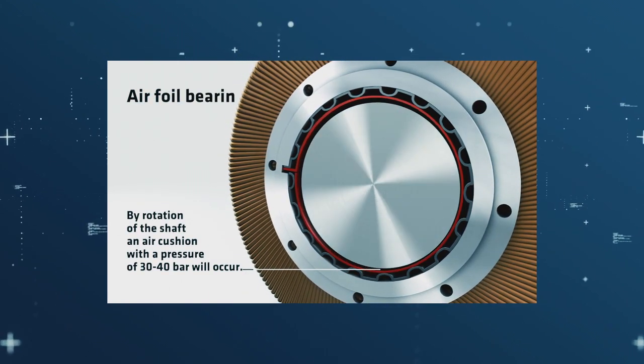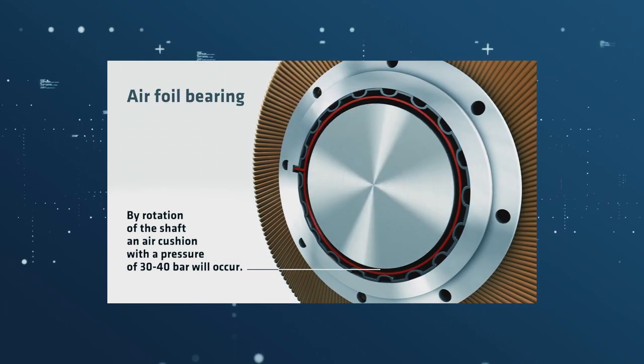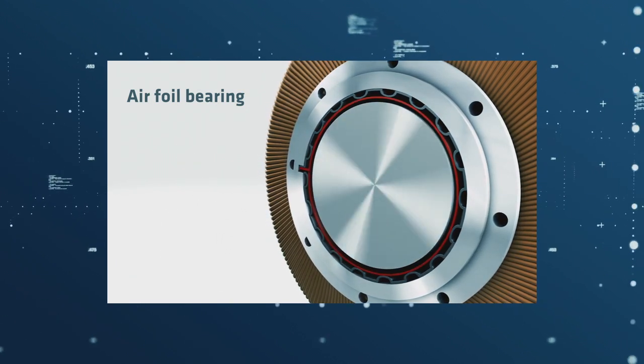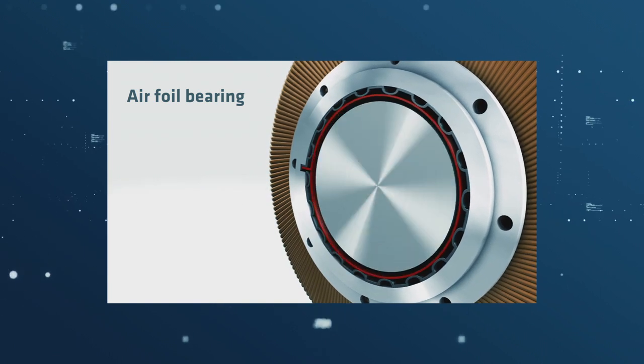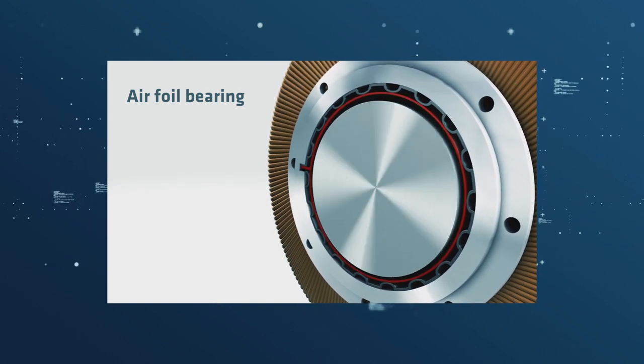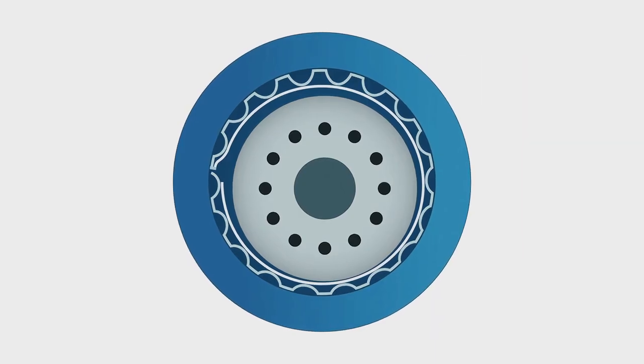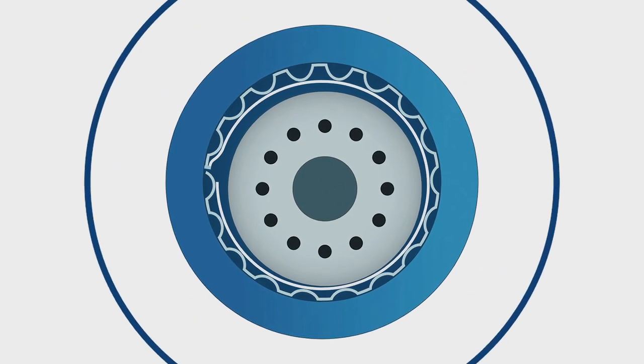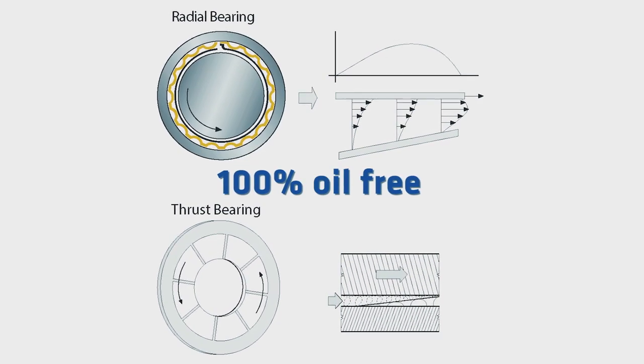The key technology of the Aerzen Turbo Blower is the airfoil bearing. As it stands still, the shaft sits on a foil tightened by springs. As the shaft rotates, an air cushion forms in the bearing between the foil and the shaft. This air cushion maintains the shaft in suspension without any need for an external source of compressed air. The bearings are not lubricated and the system is absolutely oil-free.